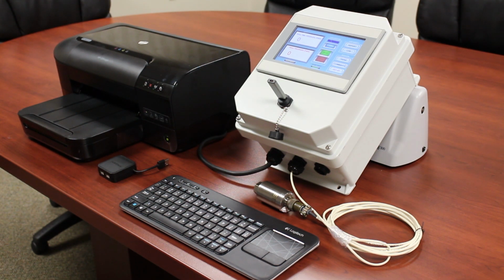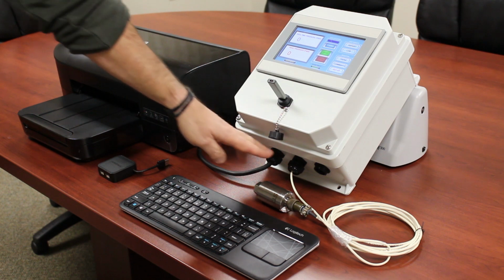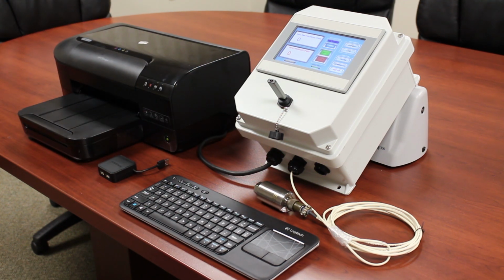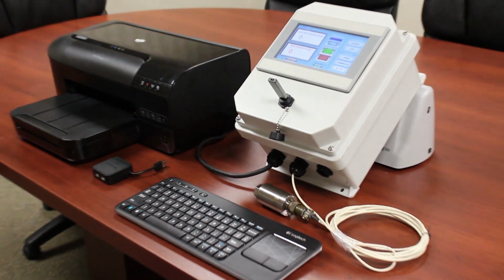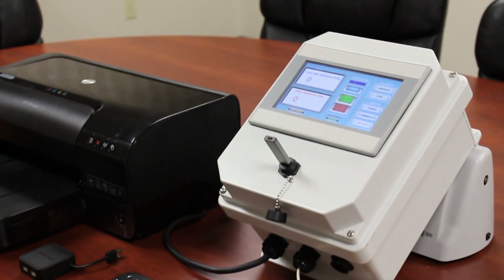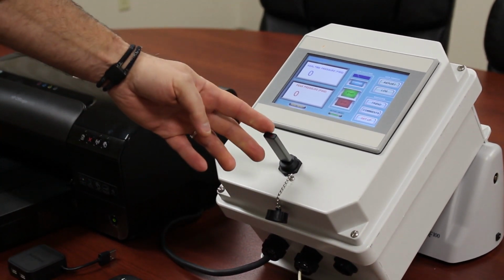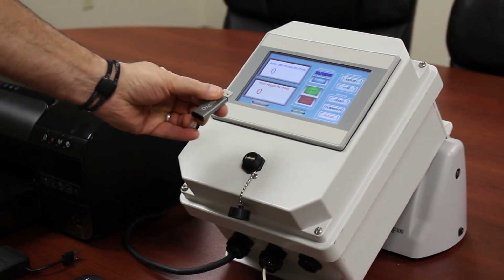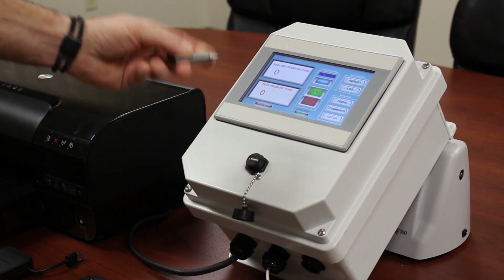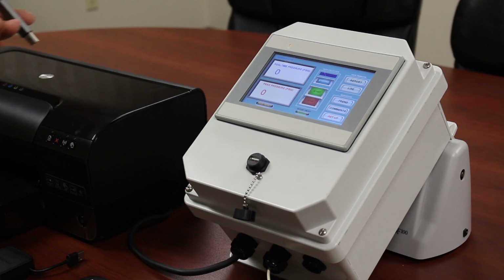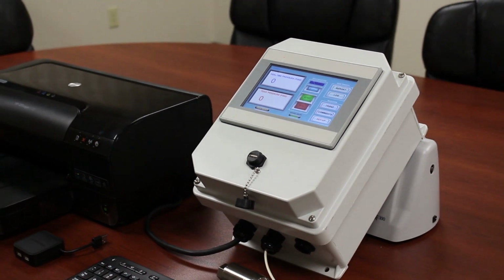Some of the other options you can get also are temperature, and you can get the unit with dual pressures if you want to have a low pressure transducer and a high pressure transducer. You can do that also. The unit also has an Ethernet connection at the bottom. You can plug the unit directly into a computer to send your data directly to the computer, or you can send it to the USB drive that's inserted into the front of the unit. Take your data from there and take this stick to your computer and print your test report out from there.